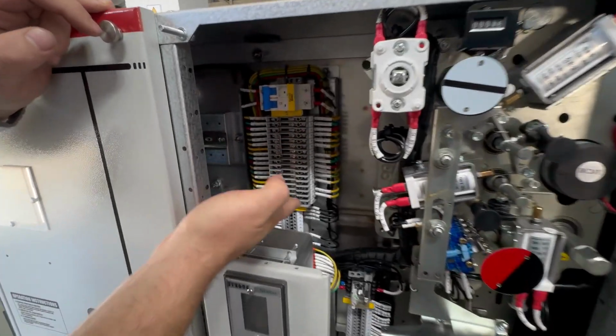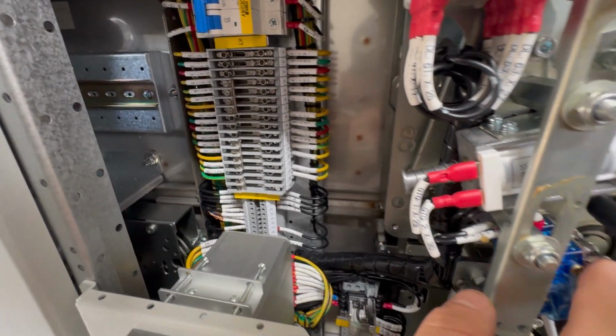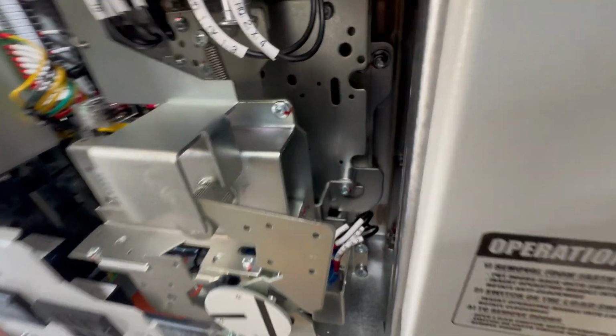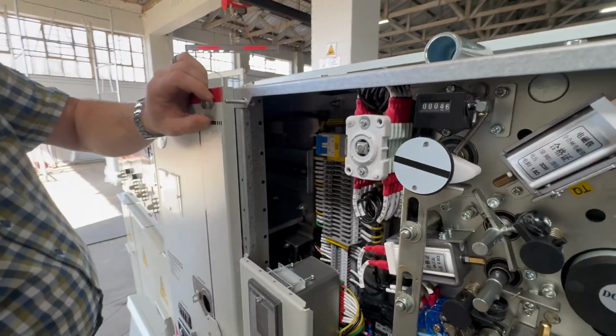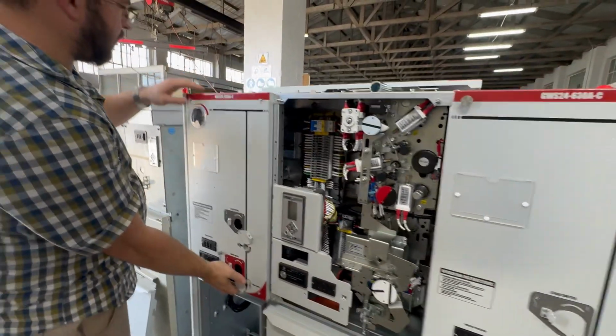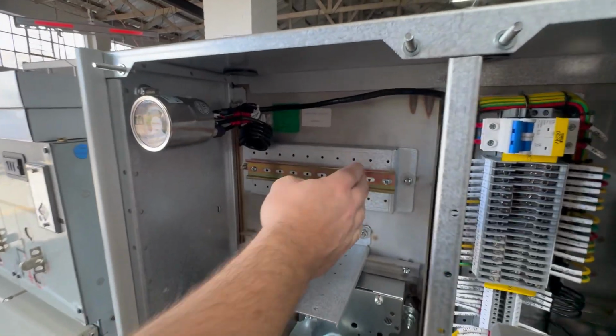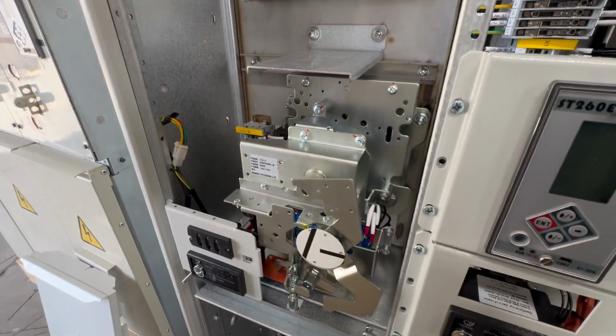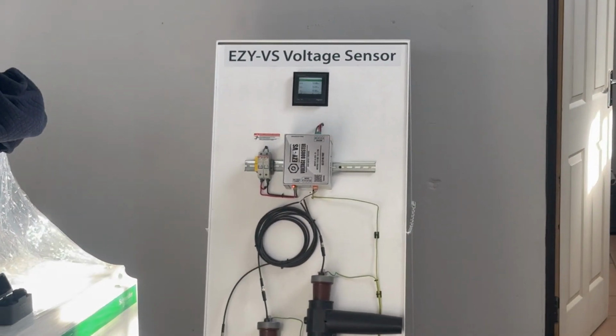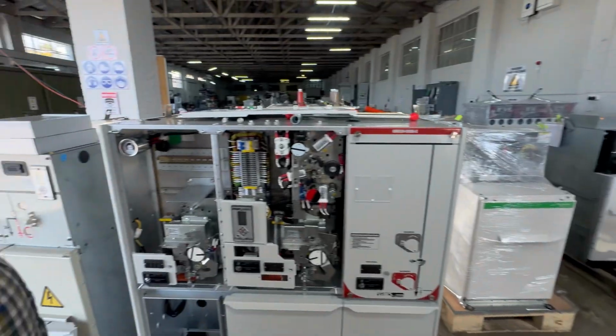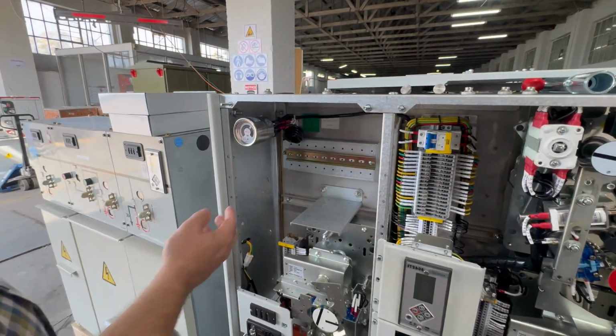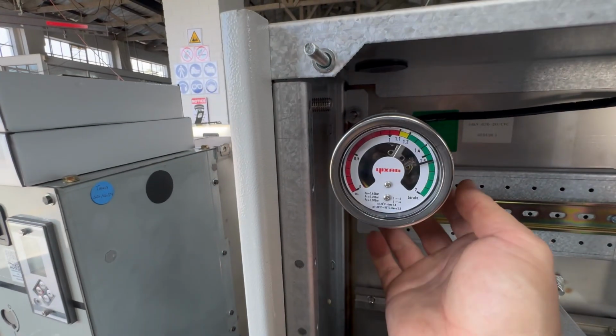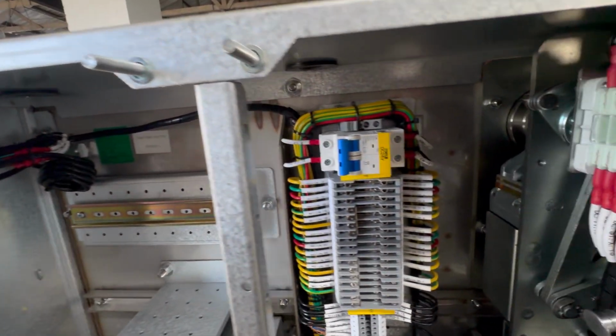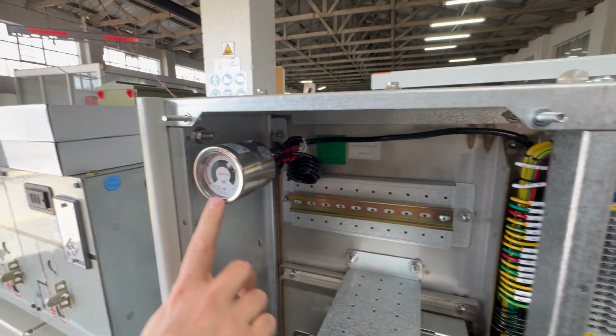You've got your CT test blocks. You have all of these connectors, such as all of these statuses, and the statuses of your earth switch, and all of the statuses are there on the counter that I already showed you. And then on this side, on the isolator side, you will see that it has got a lot of space and an extra DIN rail for you to maybe put some extra terminals, or you can put the EasyVS voltage sensor set in to replace a VT, and then you can make this a bulk metering unit very simply. You don't need extra space and extra enclosures. The manometer, the gas density meter, also has got contacts, and it's already wired in if you want to use remote switching and you are scared of maybe the SF6 will be this or that. We have got that standard built into this unit.